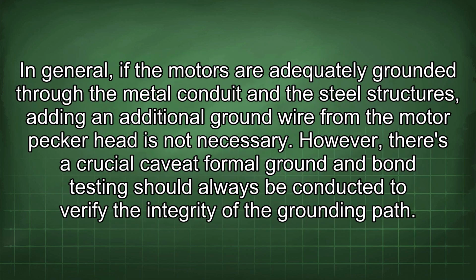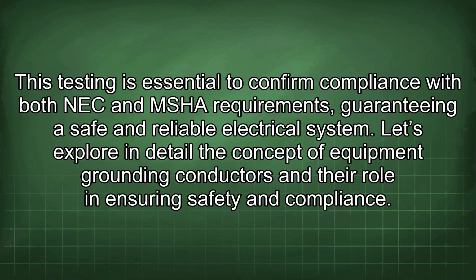In general, if the motors are adequately grounded through the metal conduit and the steel structures, adding an additional ground wire from the motor pecker head is not necessary. However, there's a crucial caveat: formal ground and bond testing should always be conducted to verify the integrity of the grounding path. This testing is essential to confirm compliance with both NEC and MSHA requirements, guaranteeing a safe and reliable electrical system.